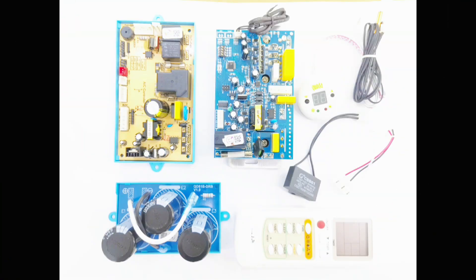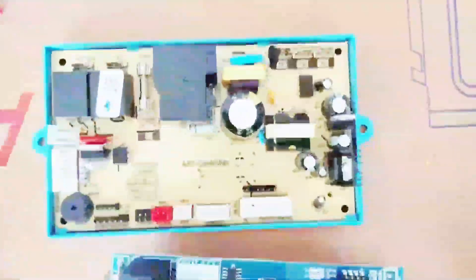The indoor PCB can be connected to an AC or DC blower motor, as in the original unit. If the blower motor is AC, a starter capacitor is provided. Swing louver motor can also be connected without trouble.